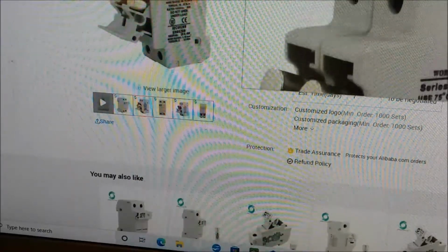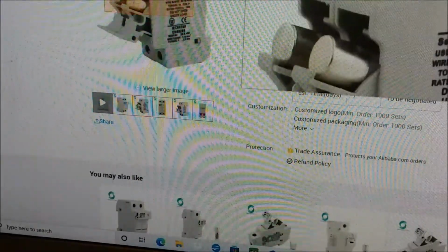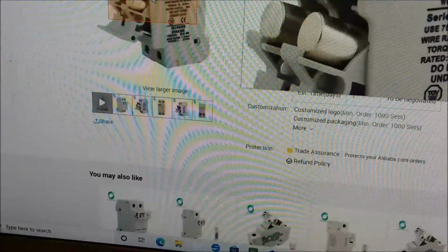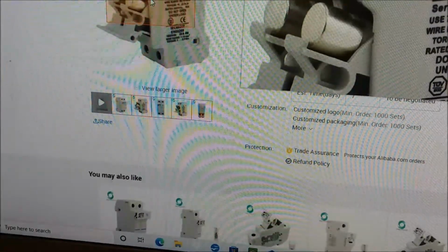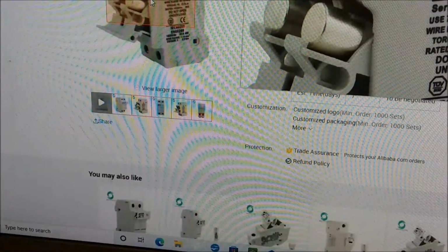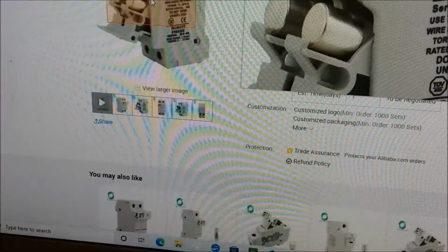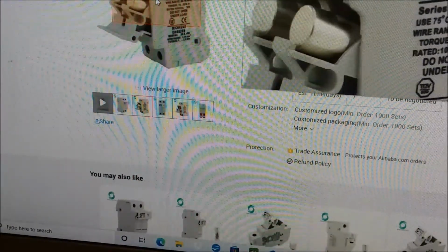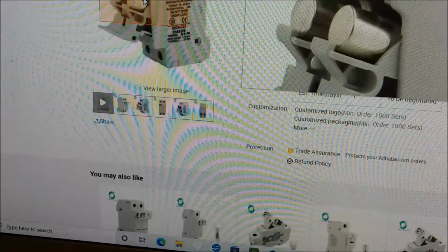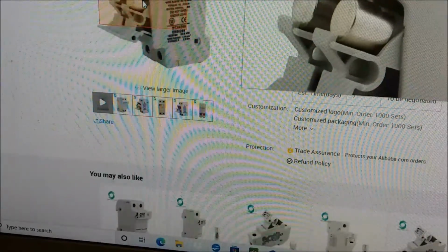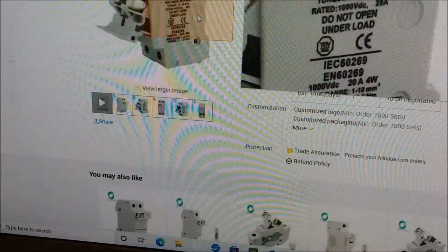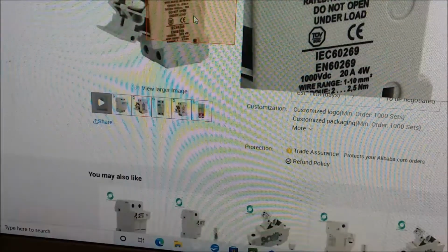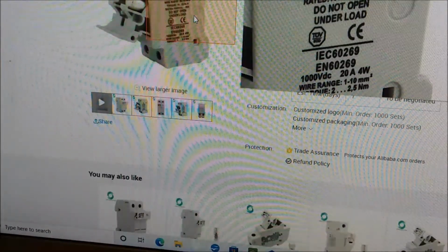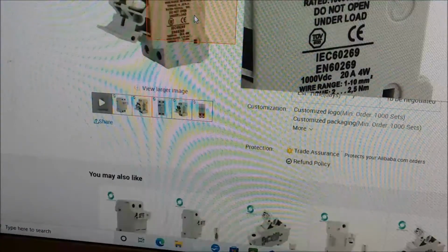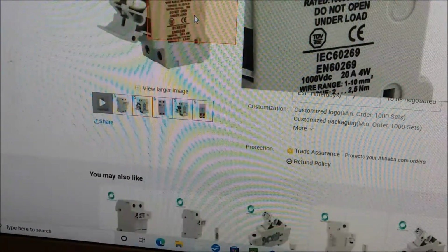The advantage to this one is it's a pair, so your positive and negative wires are both fused, and they're on the same block. So if you have a string coming in, you can have a pair of fuses for each string, and then a spacer - basically an end block for a DIN rail - you put between them to separate them so you can tell which two goes with which.